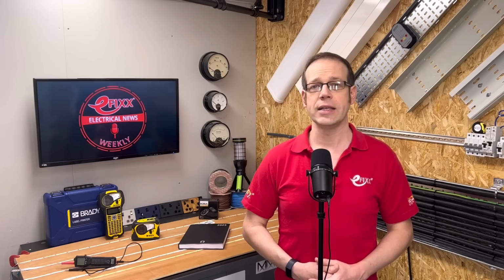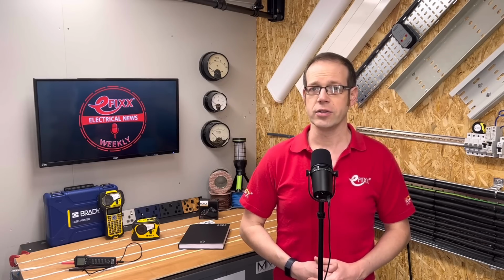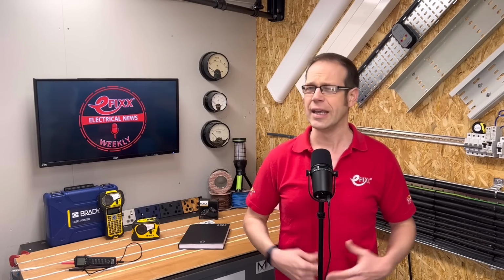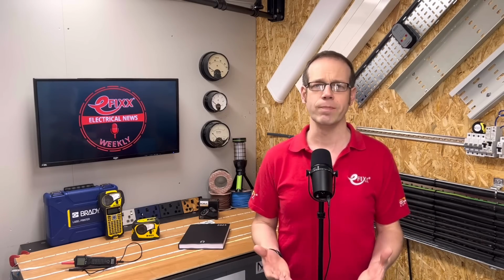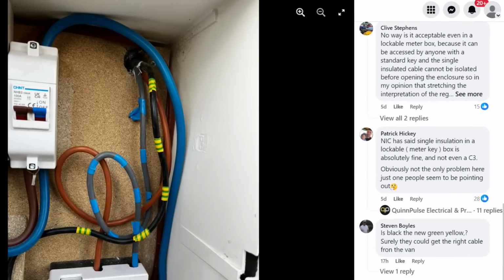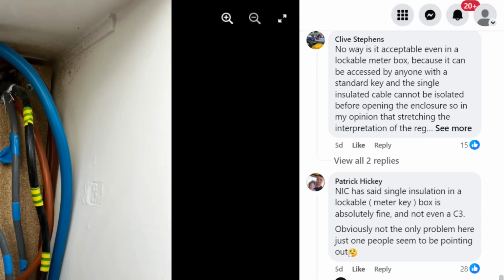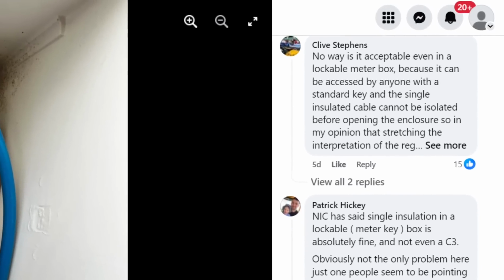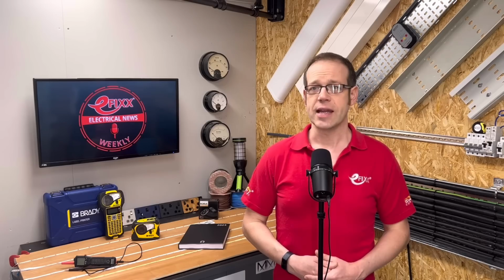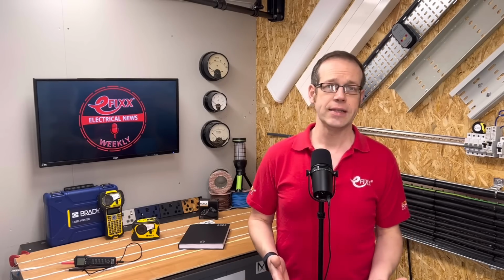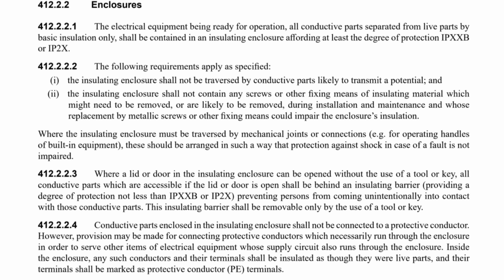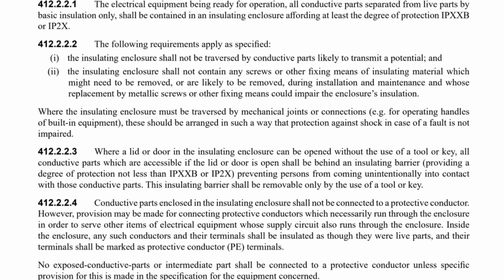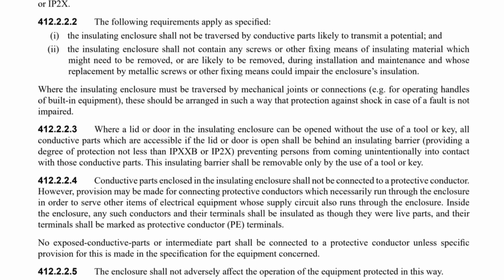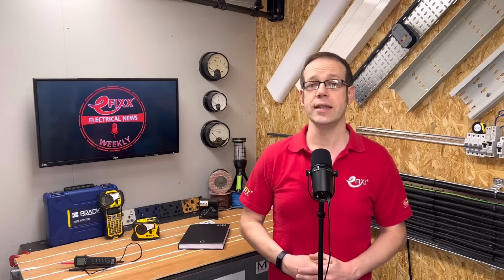Electrical work in new build housing is fiercely competitive, and this method is considerably cheaper and faster, but many electricians regard this as bad practice and question how the installation can be approved for connection. They say that single insulation provides only basic protection and can be damaged during installation or alteration. They also argue that the meter cabinet is accessible to the householder, albeit with a simple tool. Customers can use a standard triangular key to open the box and read their meter. While a meter cupboard appears to comply with Regulation 412.2.2, in practice it is readily accessible to unskilled people. In which case, say the critics, the conductors need double protection.